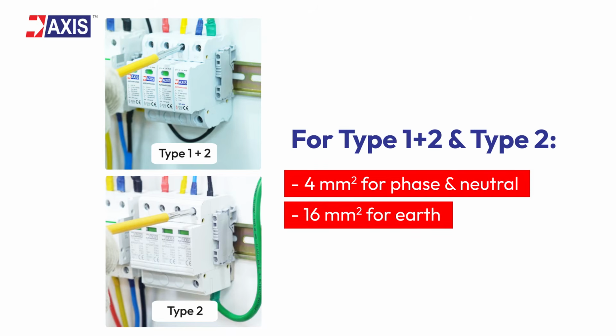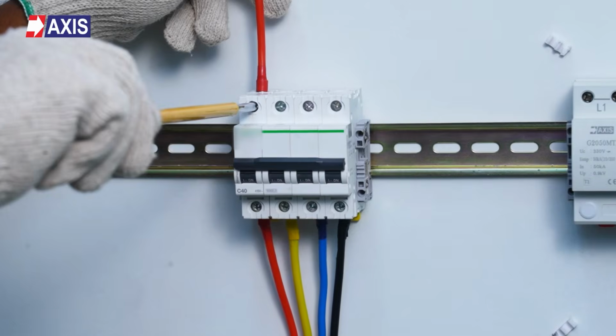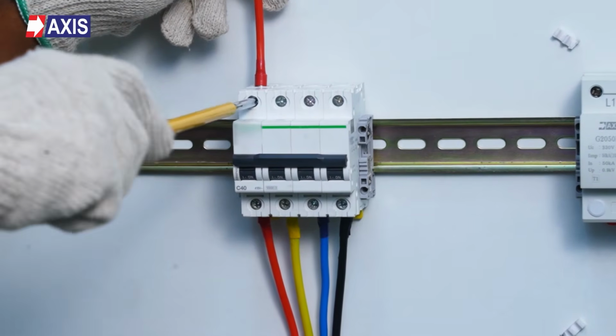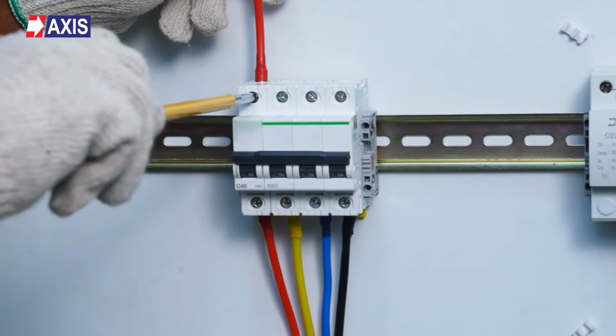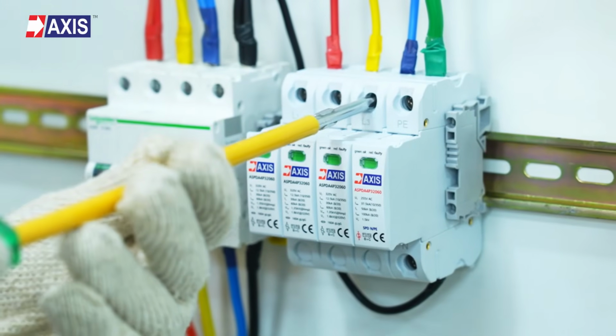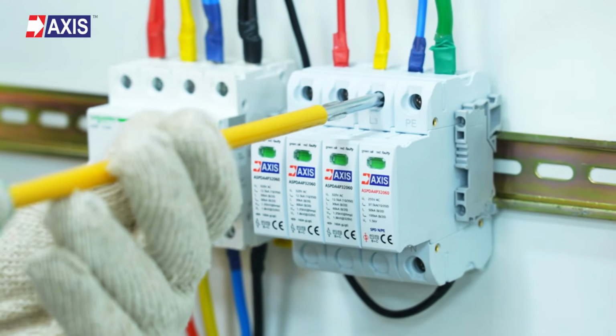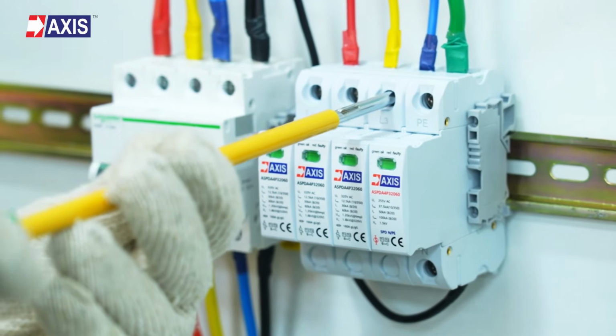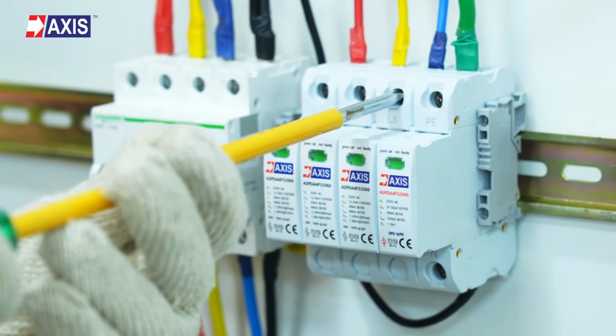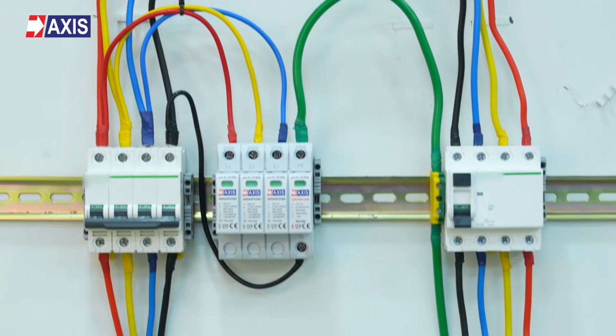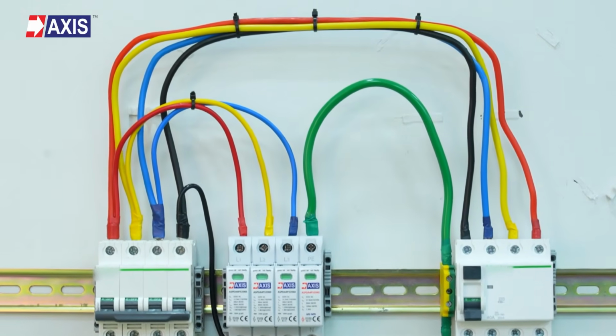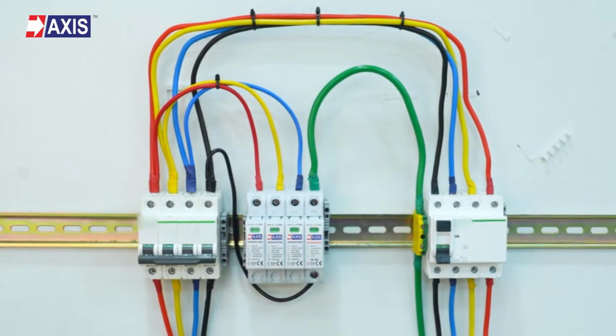In this case, for installing Type 1 plus 2 and Type 2 SPDs, the supply is already connected to the MCB's incoming terminals. We just have to connect the outgoing terminal of the MCB to both the SPDs and the load or RCCB in a parallel connection. The installation process is the same as before. This completes our installation.